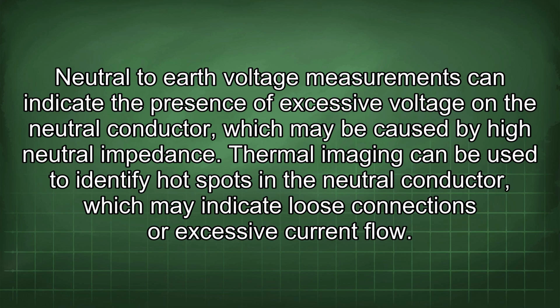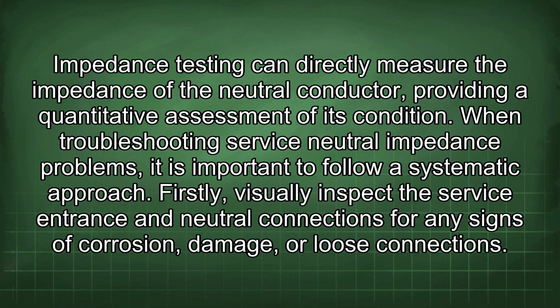Neutral-to-earth voltage measurements can indicate the presence of excessive voltage on the neutral conductor, which may be caused by high neutral impedance. Thermal imaging can be used to identify hot spots in the neutral conductor, which may indicate loose connections or excessive current flow. Impedance testing can directly measure the impedance of the neutral conductor, providing a quantitative assessment of its condition. When troubleshooting service-neutral impedance problems, it is important to follow a systematic approach.